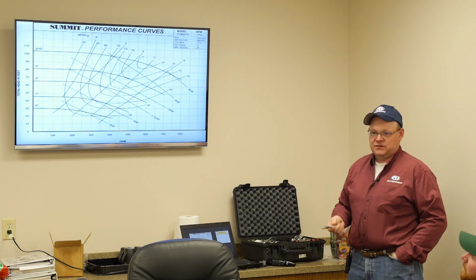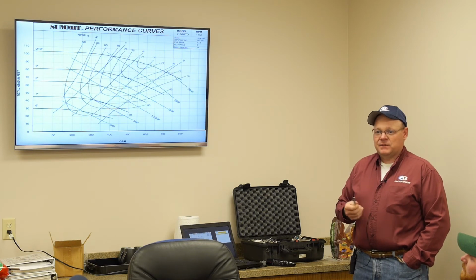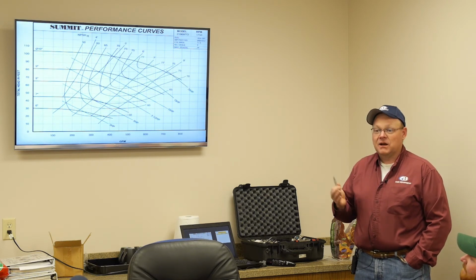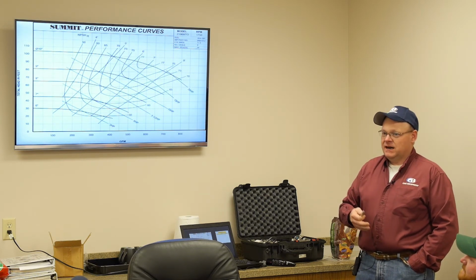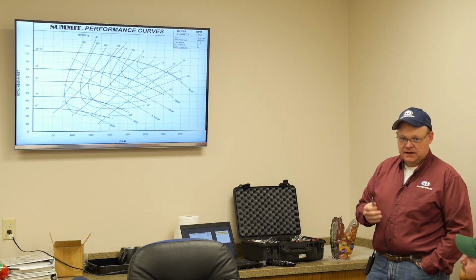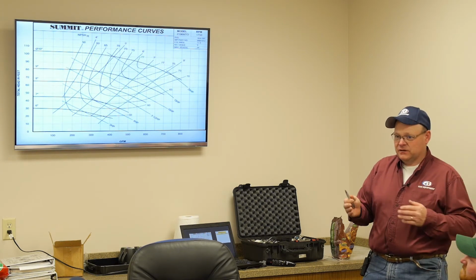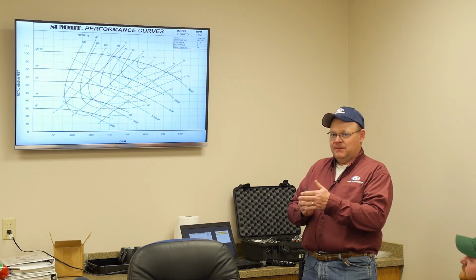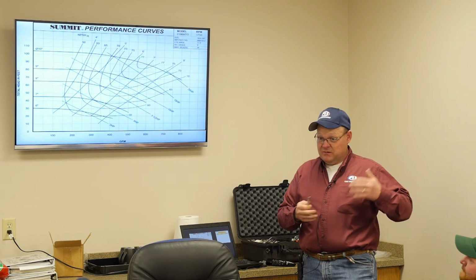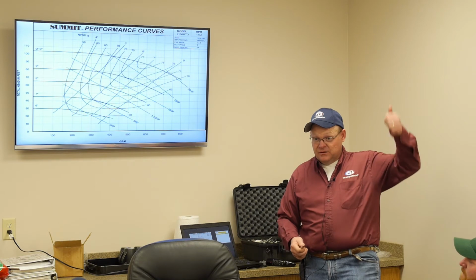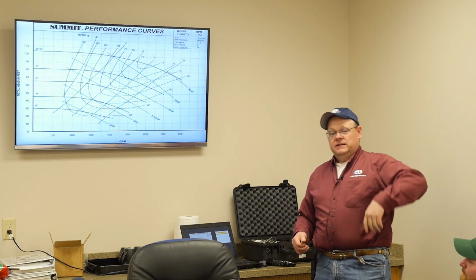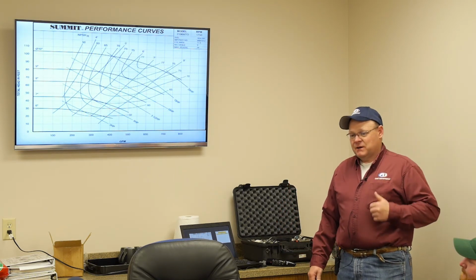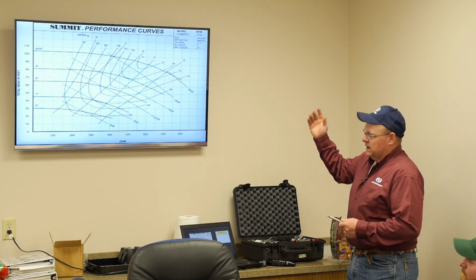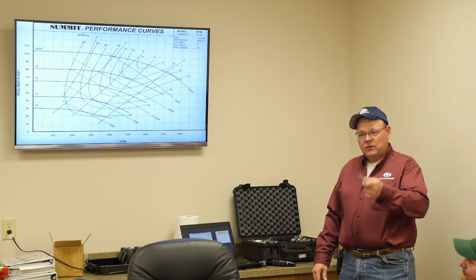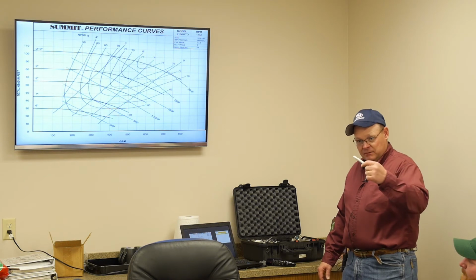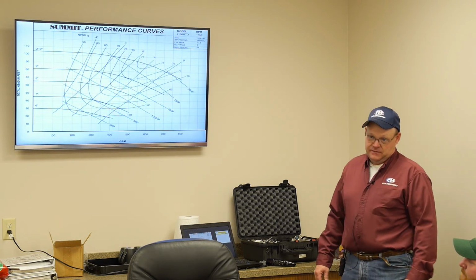I'll just put this bigger. I got the same pump and everything in there. I don't want to change all the plumbing that it may require, but I need twice the flow. And I know that if I have twice the flow, my friction loss to get the fluid through the pipe is going to exponentially double. I'm going to put twice the flow in it, so my pressure's going to go way up really quick. That's all right. Hell, I can buy 100 horsepower motors every day. So I just stick that on there. But they always forget that they may not be physically able to get it into the pump.